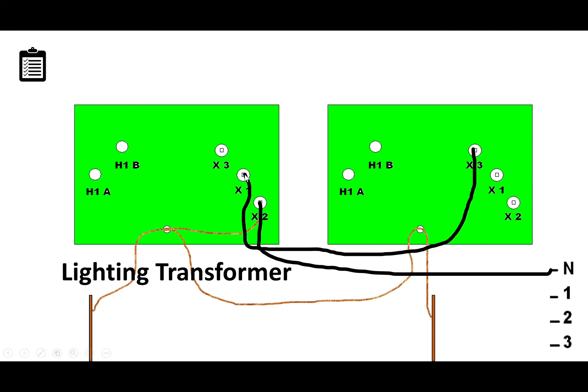After that, we're going to connect the X1 of the lighting transformer to the X3 of the power transformer. This transformer on the right we're calling the power transformer. It's generally a little smaller KVA as well. We're doing X1 to X3. We actually could have done the X3 of the left one to the X1 of the right one. It really didn't matter. In this case, I chose the X1 to the X3.